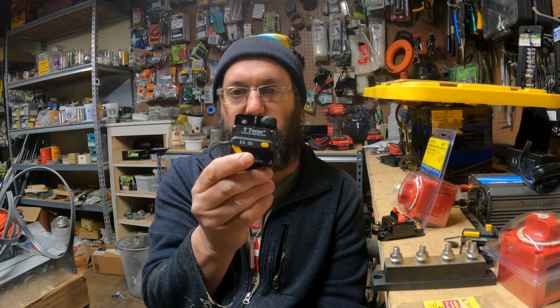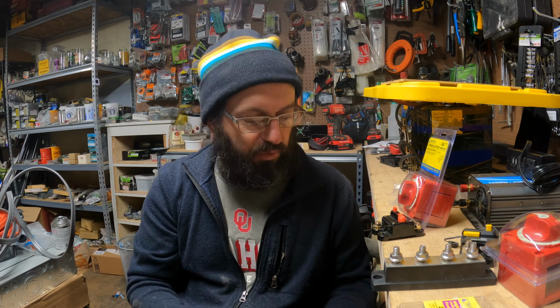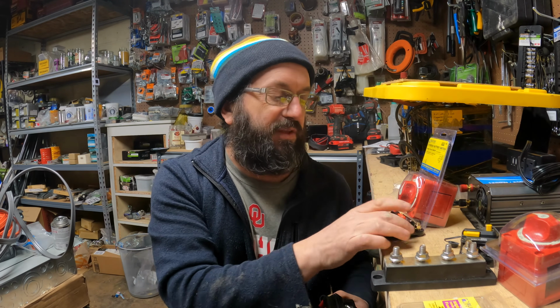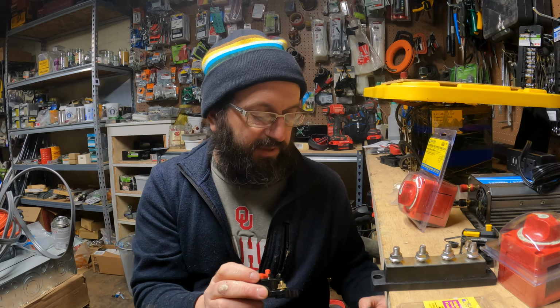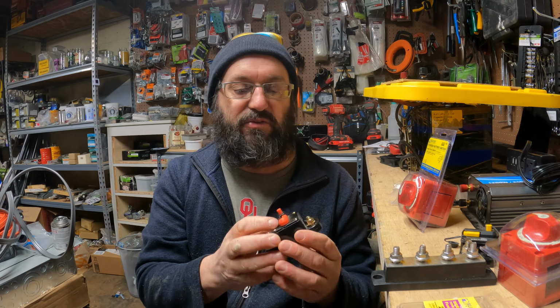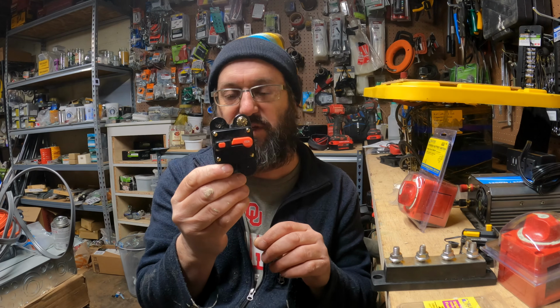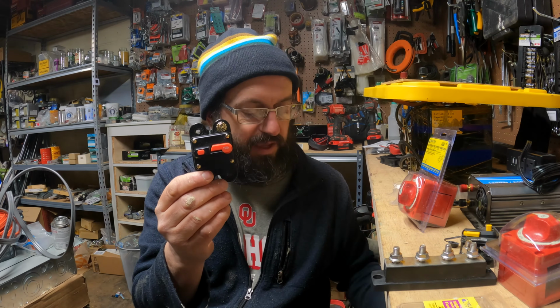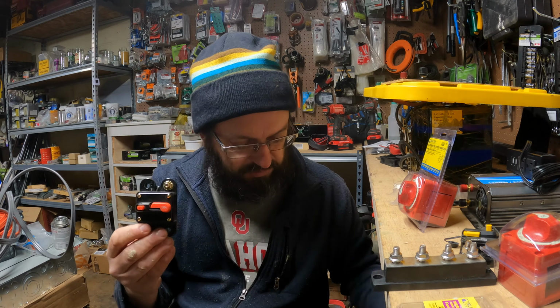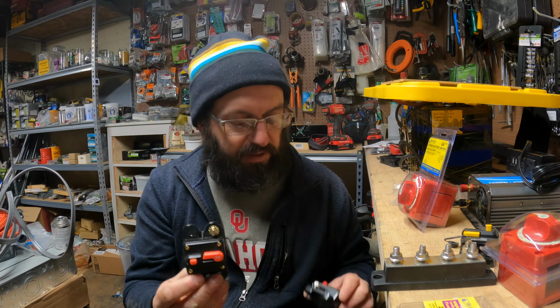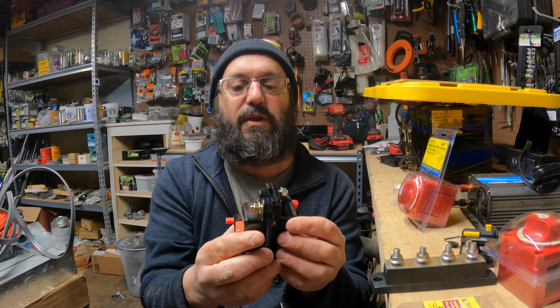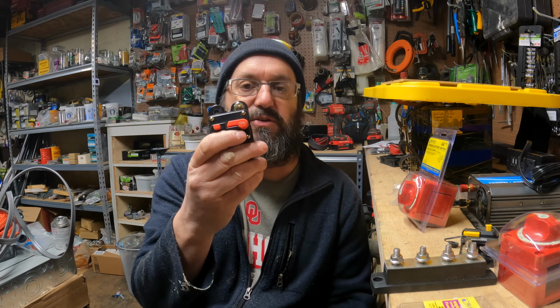I'd recommend you use Bussmann fuses, or at minimum this type of fuse, because one thing I've noticed about fuses that drives me crazy is these cheap fuses you get on Amazon, like this one, say 150 amps, but it's the exact same size as this one that's rated 50 amps. So there's no possible way this thing is actually going to do 150 amps. You've got to be careful.